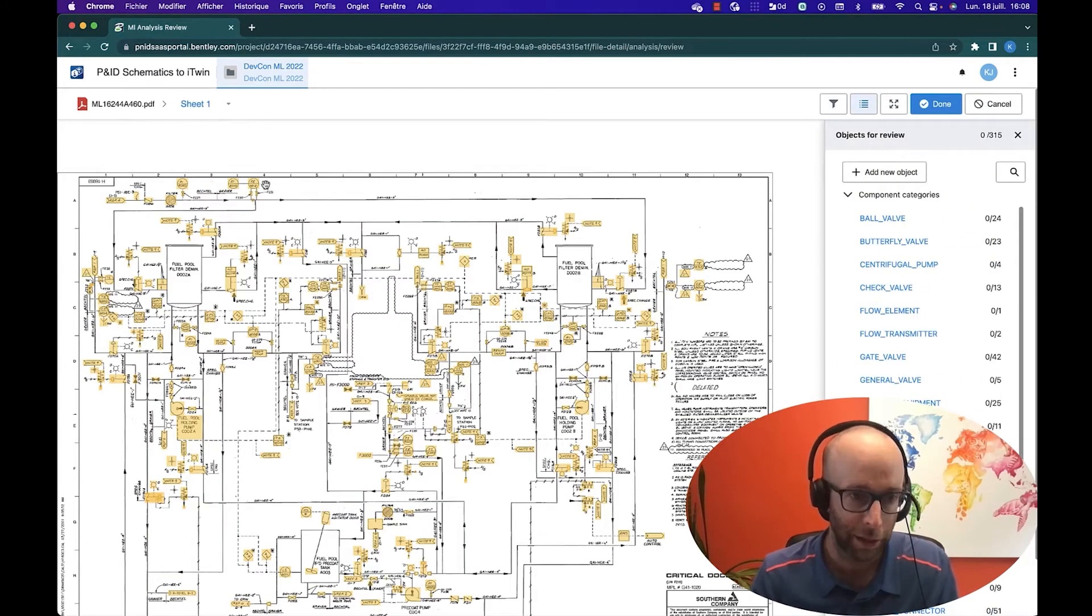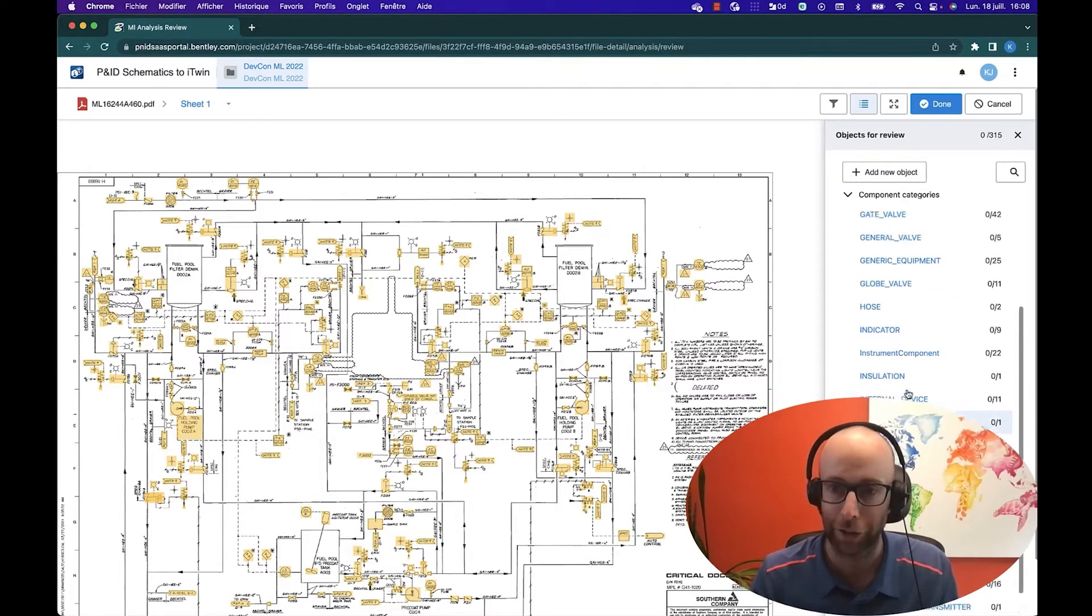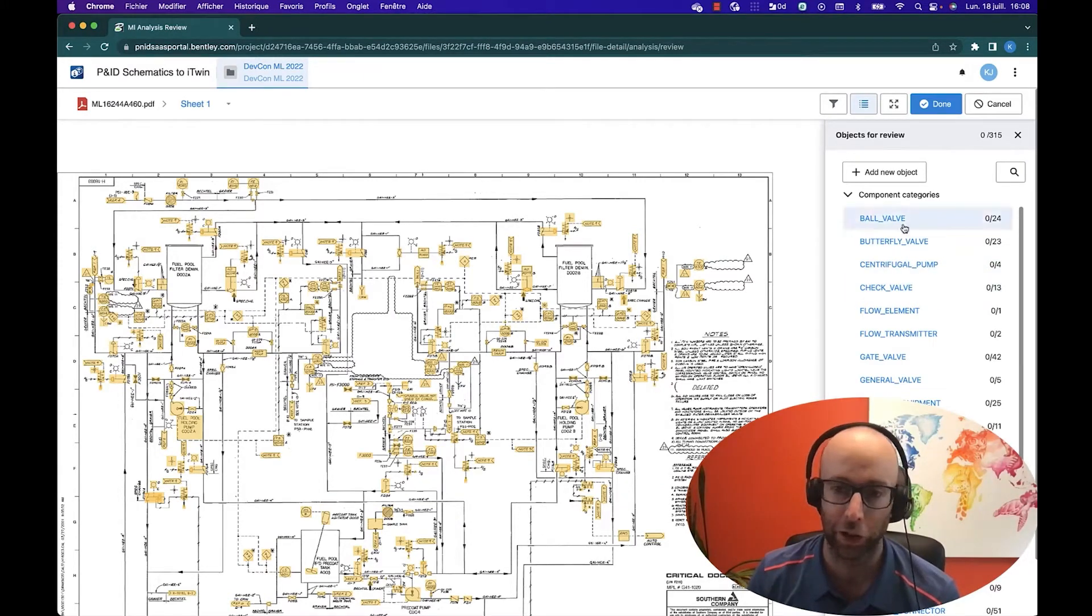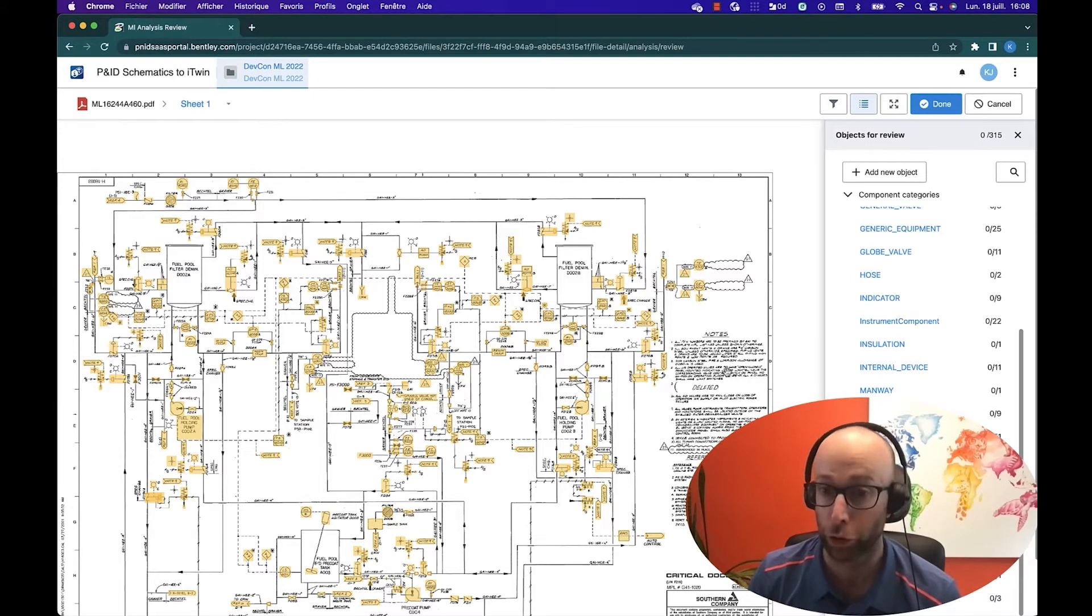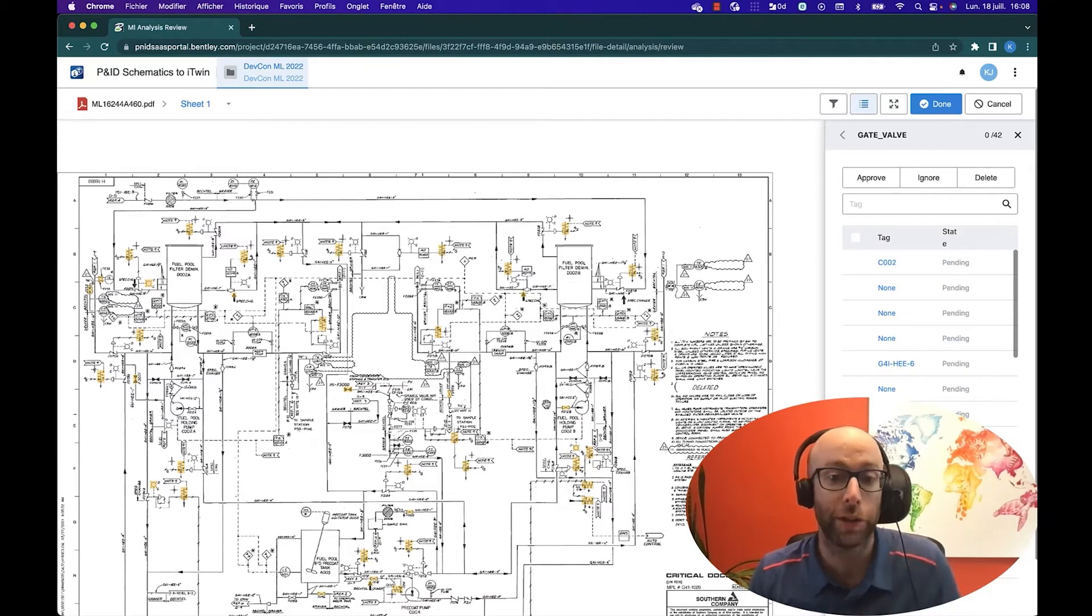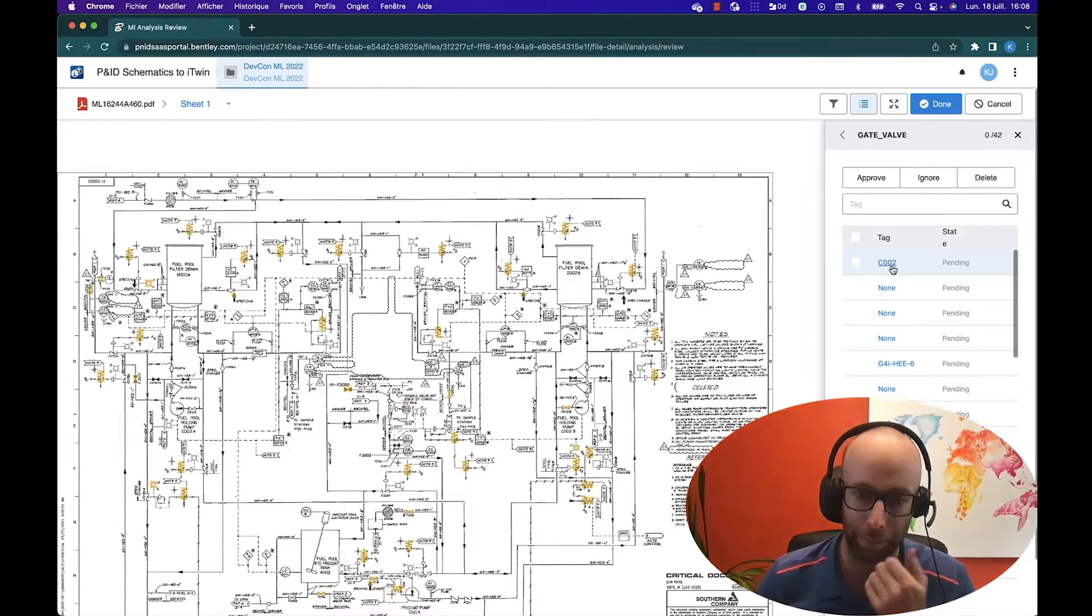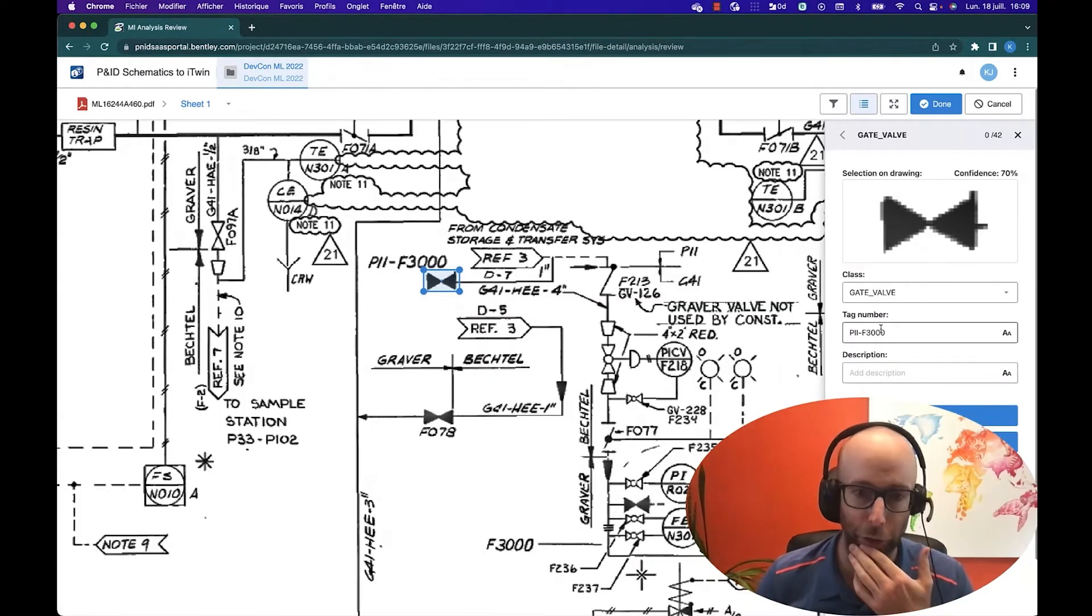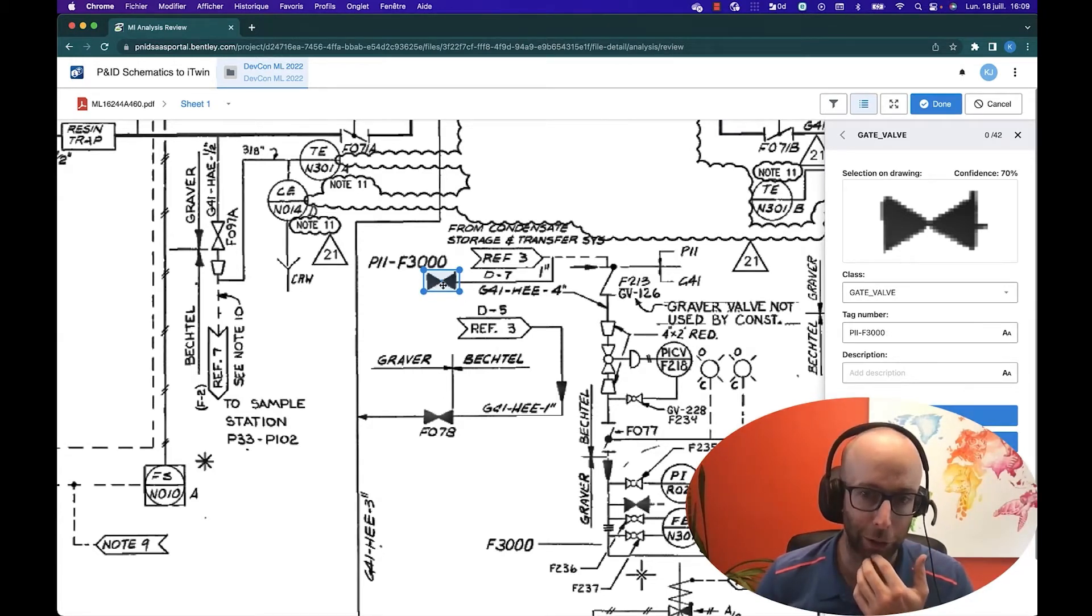I'll click here and hit review process and we'll open just the first sheet for review. The first thing you'll see is yellow bounding boxes for all the elements that have been detected. We get a breakdown of the different classes that were detected. All of these classes are standard classes that are part of a standard schema. It's easy to import them later in a digital twin or in an iTwin and to cross reference whatever has been extracted here with other sources of information. We can pick any category here and we'll see all of the elements that were part of this gate valve category. The model is not only detecting the symbols and creating a bounding box around them, it's also trying to recuperate some unique tags for each of those symbols. We can classify the object by tag and then I can click on one of them and start reviewing it.